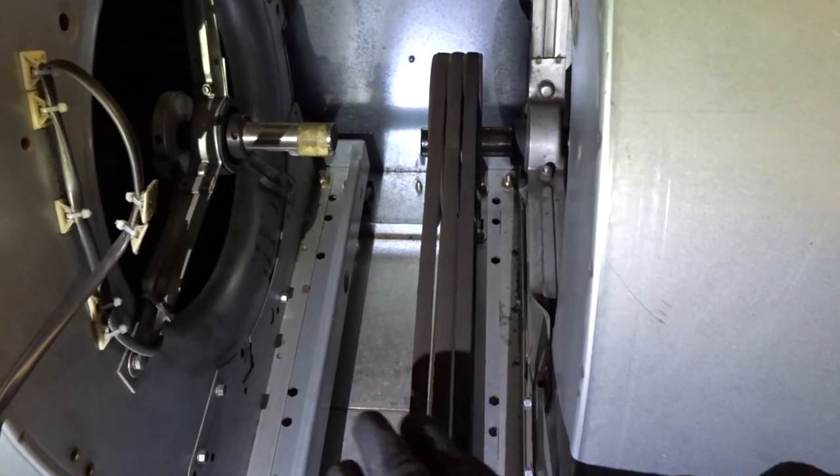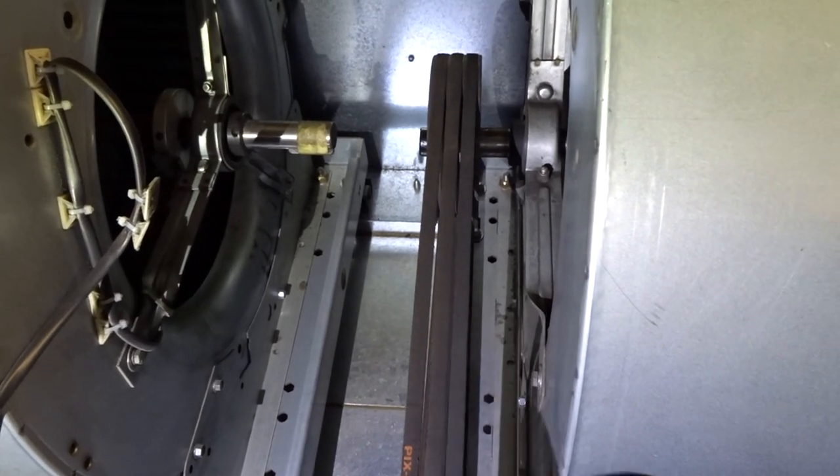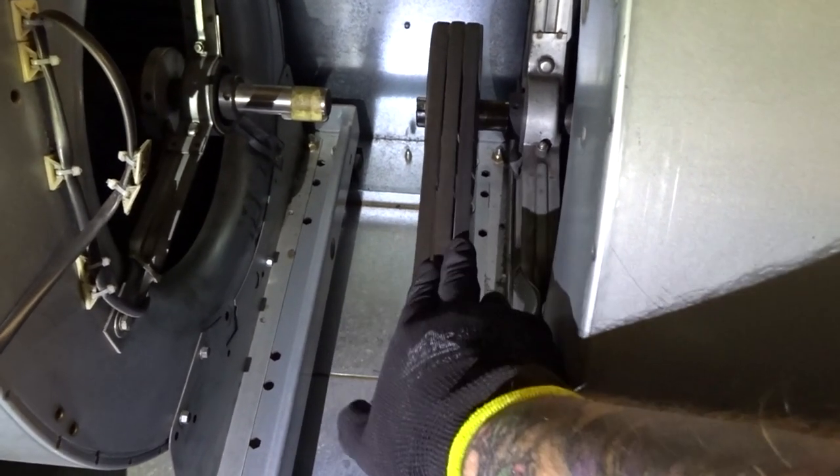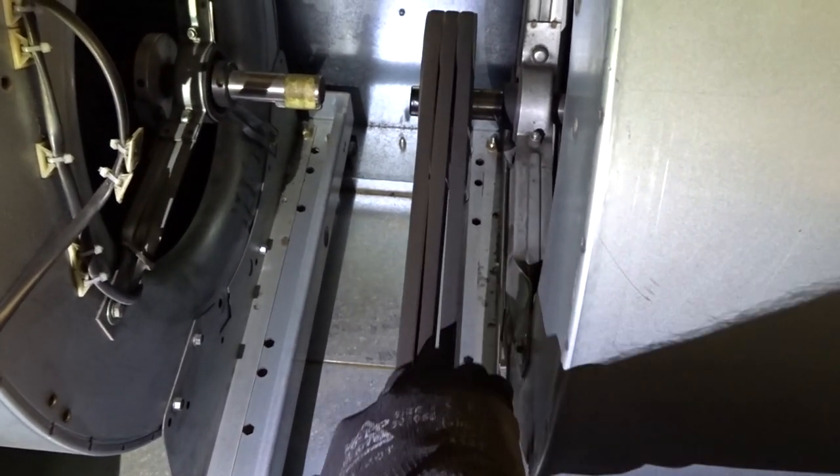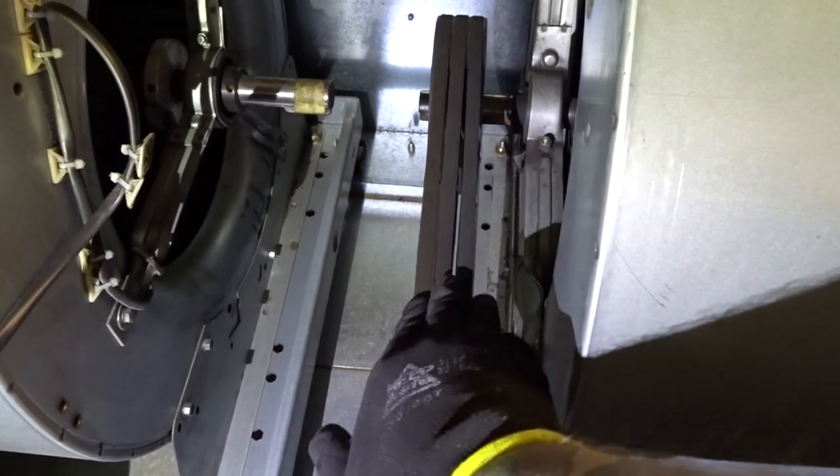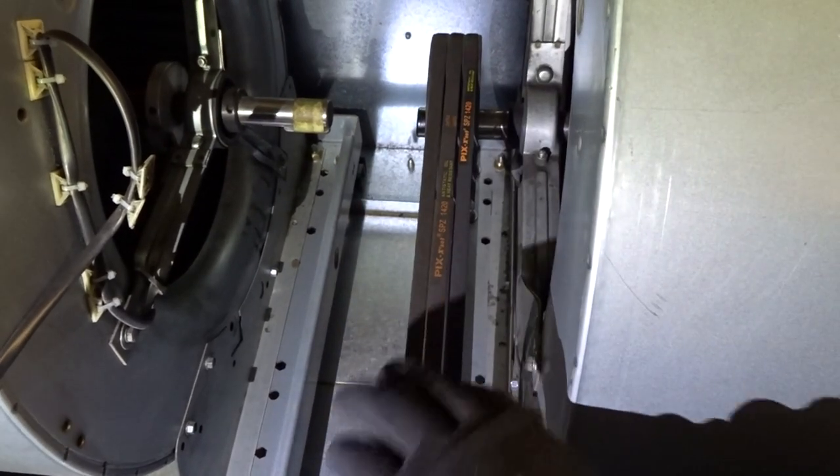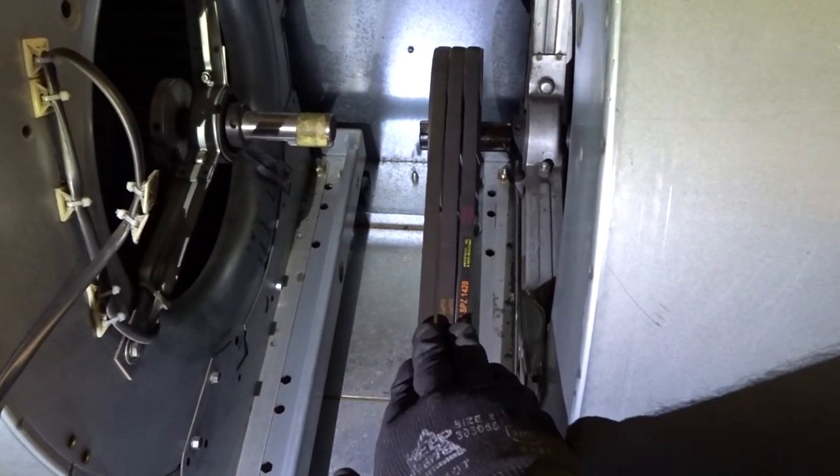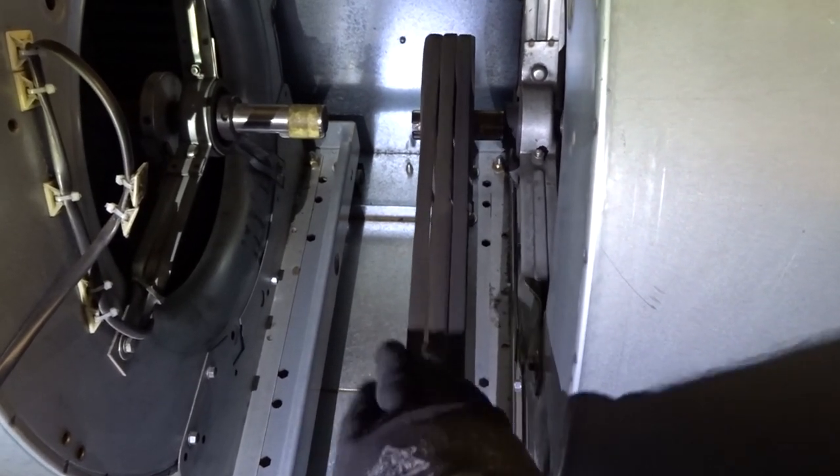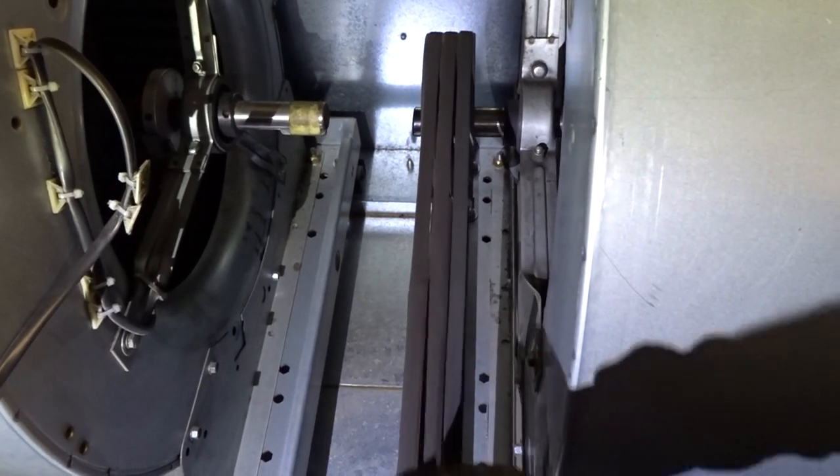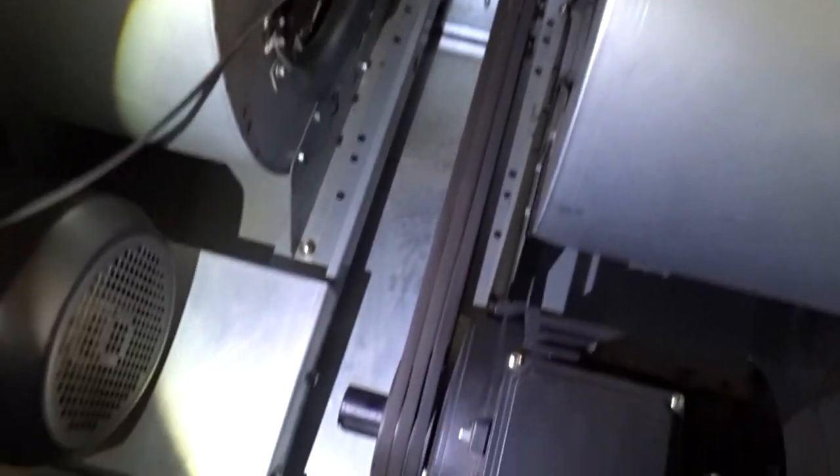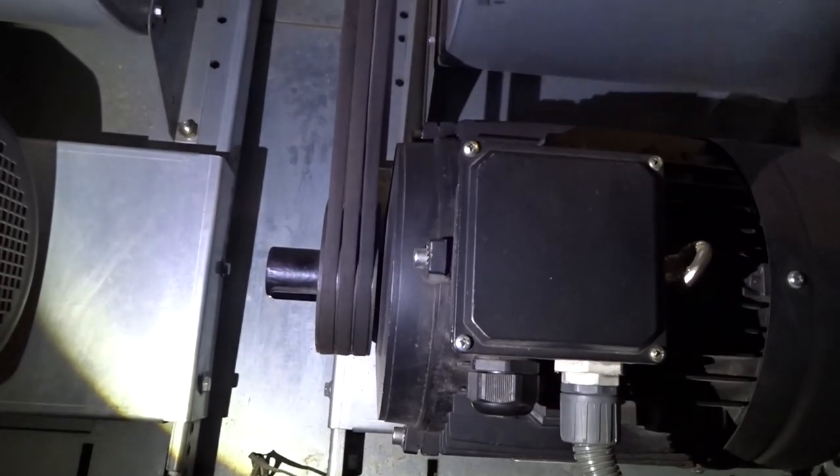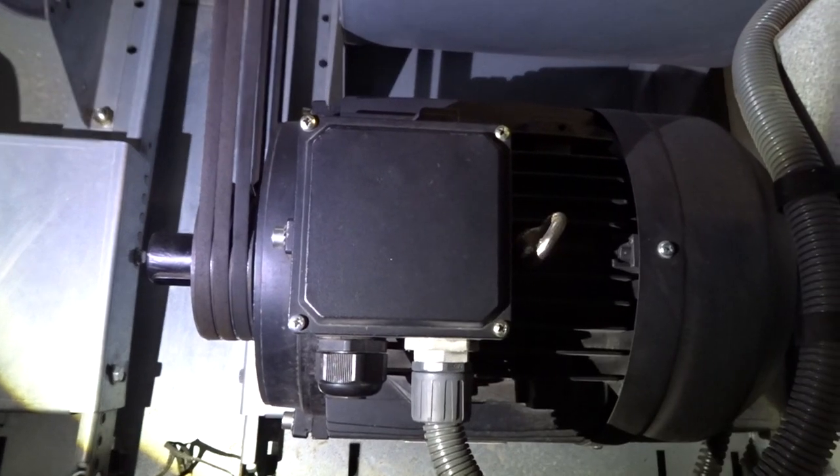We don't want that to happen because that again could cause damage to the remaining belts. It could cause damage to the left or right fan or the left or right motor. So we're just checking for any signs of fraying anywhere and any imperfections, also checking the pulleys, that the pulleys are aligned and there's no wobble and no movement coming from there. And that all seems to be in working order.